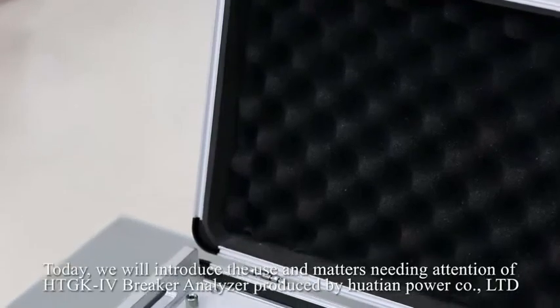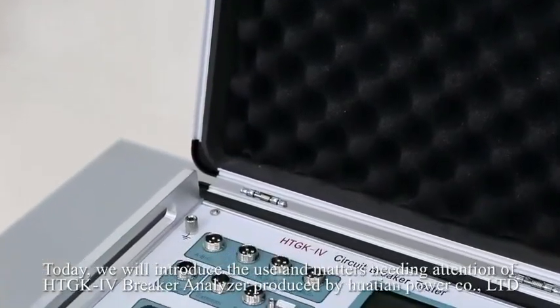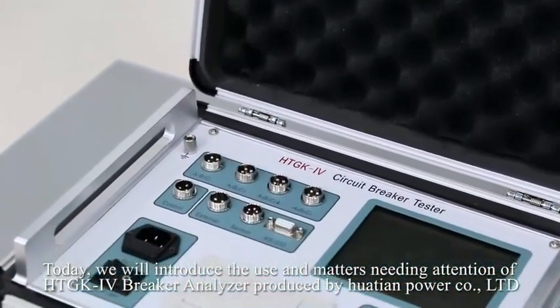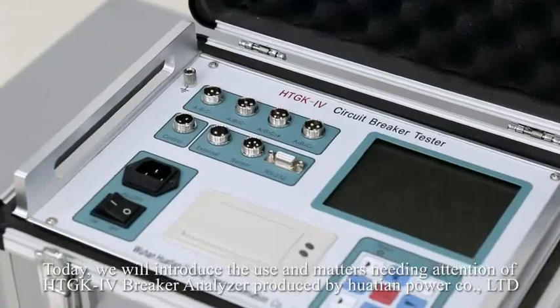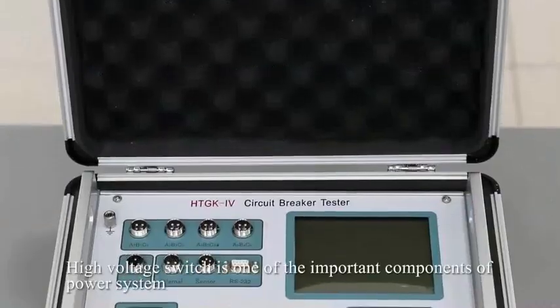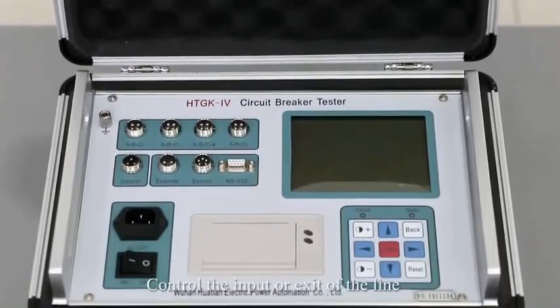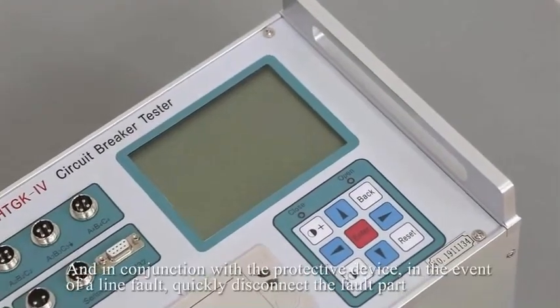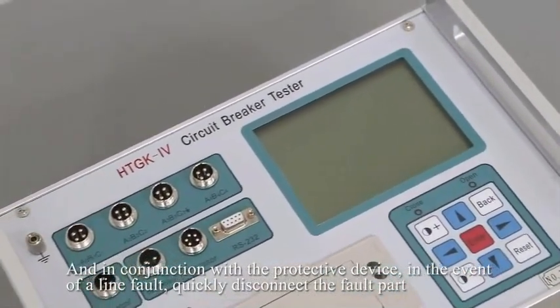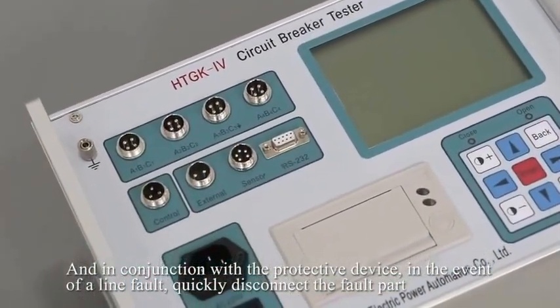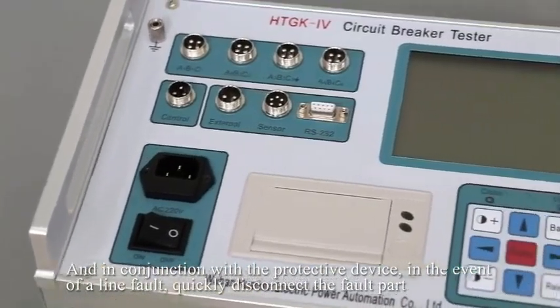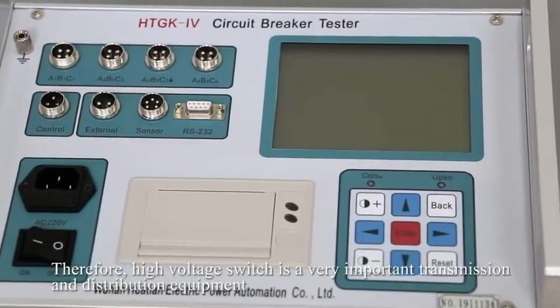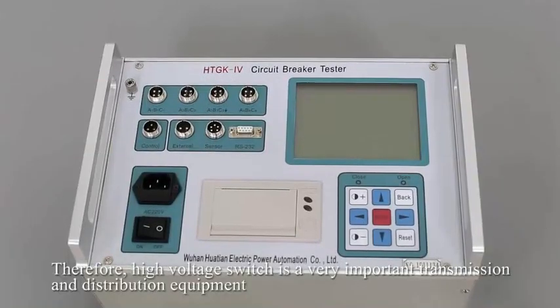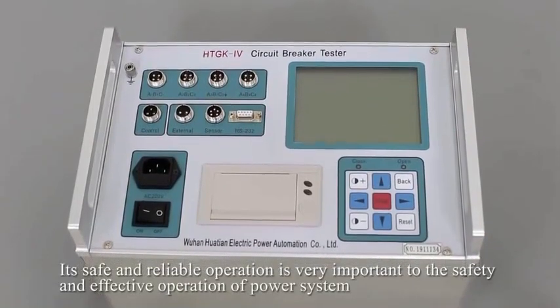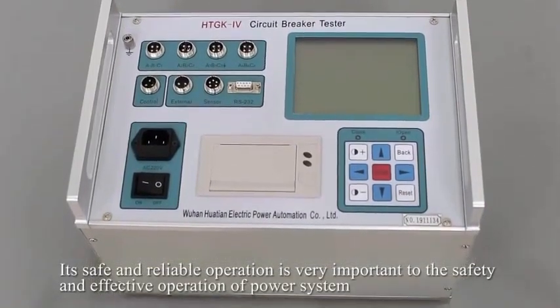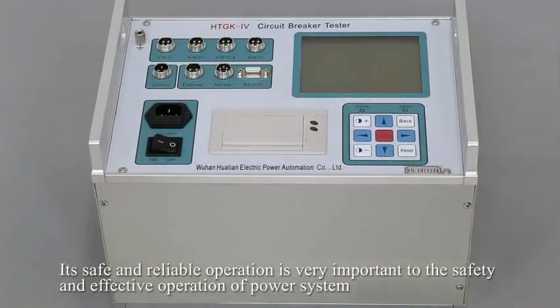Today we will introduce the use and matters needing attention of the HTGK IV breaker analyzer produced by Huatian Power Co. Limited. High voltage switch is one of the important components of the power system. It controls the input or exit of the line, and in conjunction with the protective device, in the event of a line fault, quickly disconnects the fault part. Therefore, high voltage switch is a very important transmission and distribution equipment. Its safe and reliable operation is very important to the safety and effective operation of the power system.